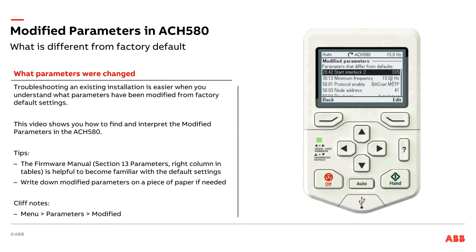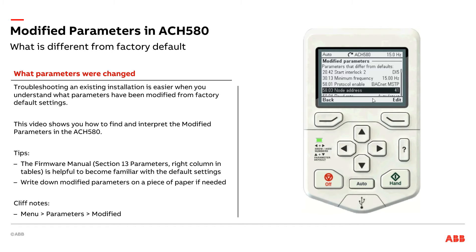I've got minimum frequency set to 15 hertz; the factory default was zero. So I don't want to go below a certain speed or frequency, so I have that set for 15 hertz. I can see that this drive has been configured for BACnet, and the MAC ID is 41. I picked that number because tomorrow happens to be my wife's 41st birthday — hopefully she never watches this video and sees that I'm talking about her age in an ABB training video.